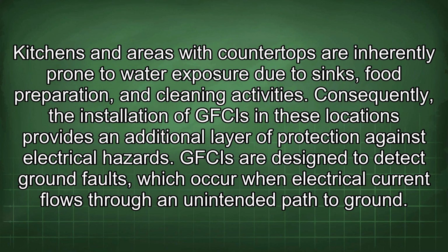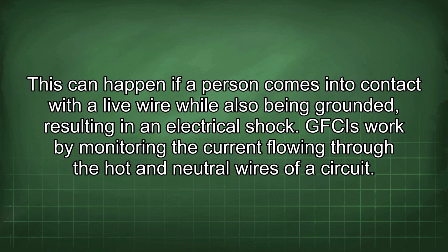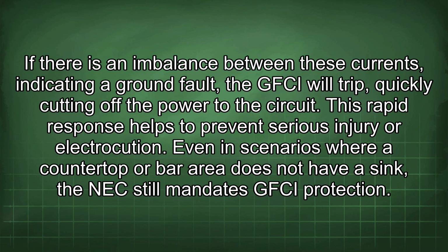GFCIs are designed to detect ground faults, which occur when electrical current flows through an unintended path to ground. This can happen if a person comes into contact with a live wire while also being grounded, resulting in an electrical shock. GFCIs work by monitoring the current flowing through the hot and neutral wires of a circuit. If there is an imbalance between these currents, indicating a ground fault, the GFCI will trip, quickly cutting off the power to the circuit. This rapid response helps to prevent serious injury or electrocution.